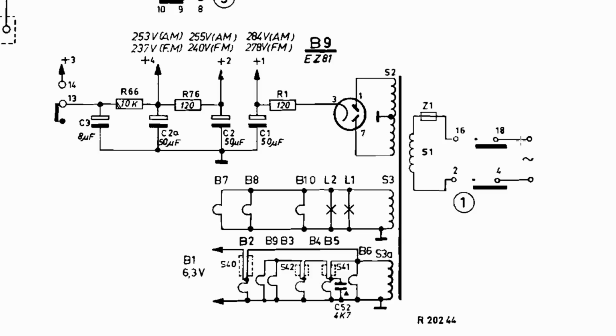But the first thing you do is measure across here. If you measure the resistance from here and flick the switch, all you're doing is measuring it through the switch to there, up there, across here, down here, across there, across there - that switch would be closed as well. And that's what you should get: the resistance of that primary winding over there.